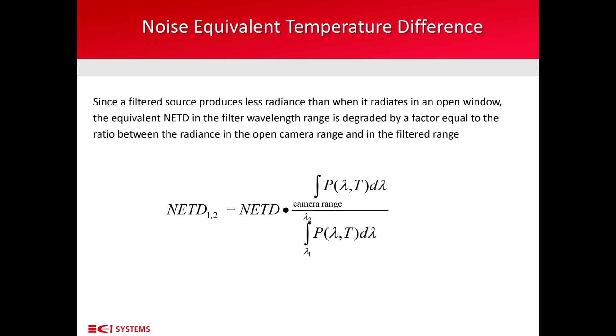The important figure of merit NETD 1,2 — on the left side of the equation — can be calculated by multiplying the noise equivalent temperature difference NETD given by the manufacturer of the camera, and multiplying this parameter by the ratio of two integrals. In the numerator is the integral of the Planck function derivative P lambda T delta T lambda over the full camera wavelength range without the filter. In the denominator is the integral of the Planck function at room temperature T within the gas absorption range lambda 1 to lambda 2.